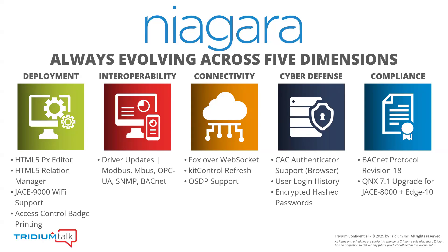For connectivity, Port 4911 is sometimes not the easiest to get open when working with IT teams. Fox over WebSockets allows for Niagara Fox traffic over Port 443. This will also be a good fallback if firewall rules or port rules are changed, allowing you to have continuous communication of your system.